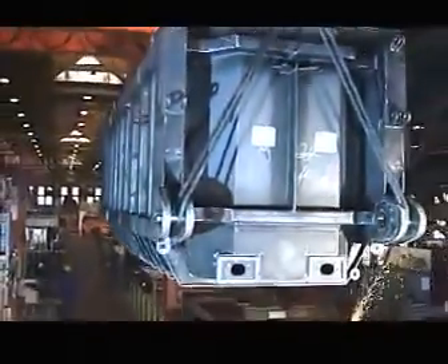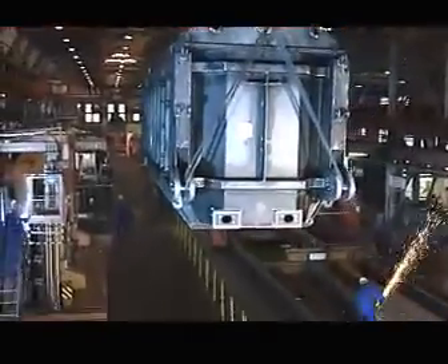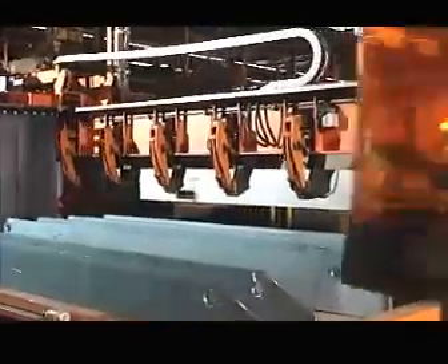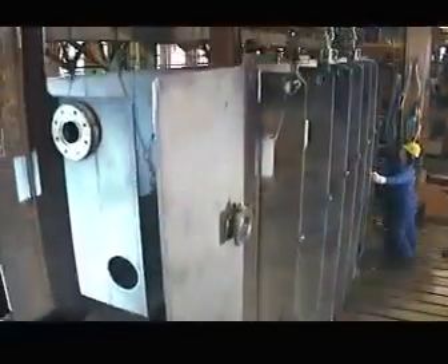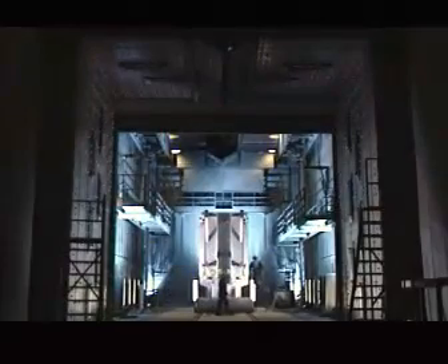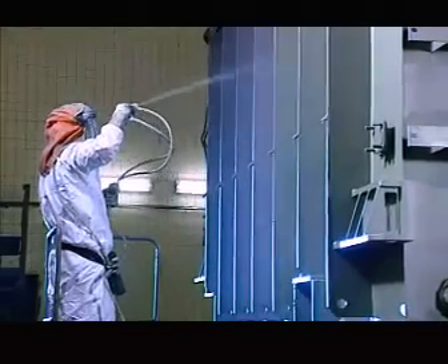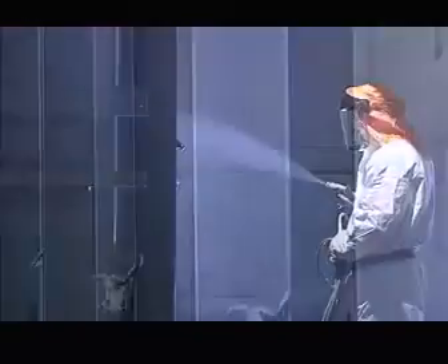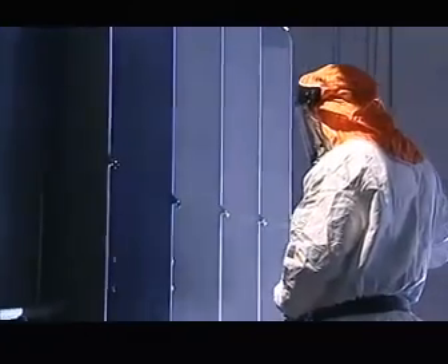The tank contains the active parts of the transformer and also the insulating oil. The total weight can be enormous, often several hundred tons. Many tanks are self-supporting. The base plates are up to 50 millimeters thick. The finished welds are tested using a non-contact fluorescence method. High resistance to corrosion is particularly important if transformers are to last well. Water-based paint is used as standard. If maximum corrosion resistance is required, then we apply an environment-friendly zinc dust coating. Afterwards comes a test for paint quality.